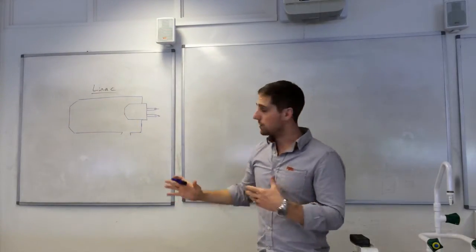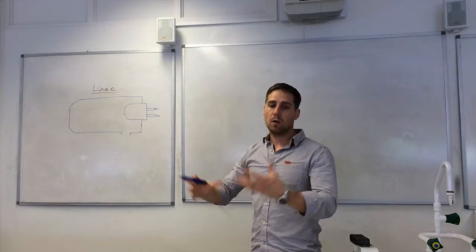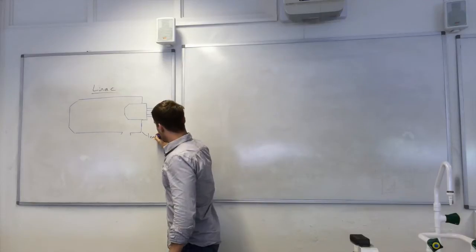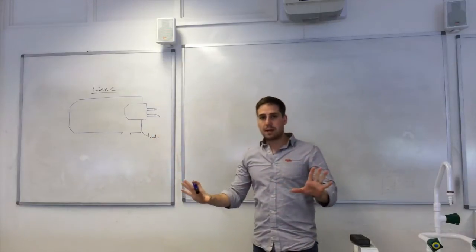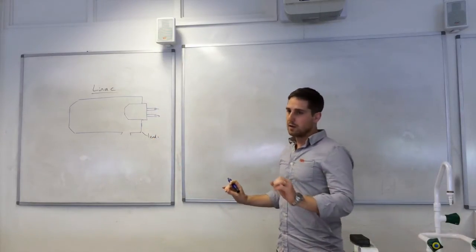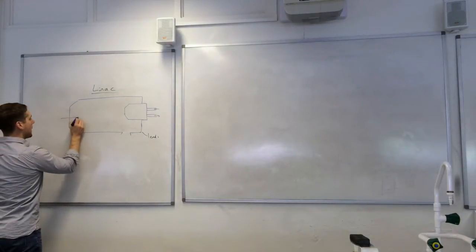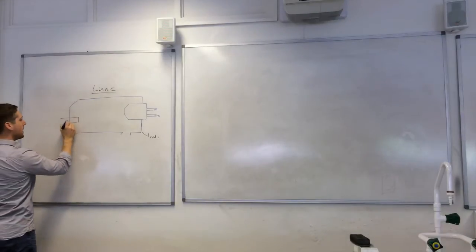Lead absorbs X-rays so it stops any stray X-rays going where we don't want them. So that's the lead casing there. There are three main components that you need to label in this linac. They are firstly, we have a cathode filament in here.